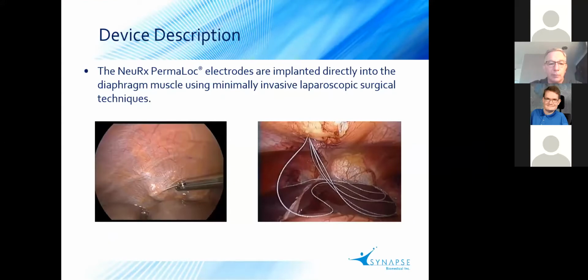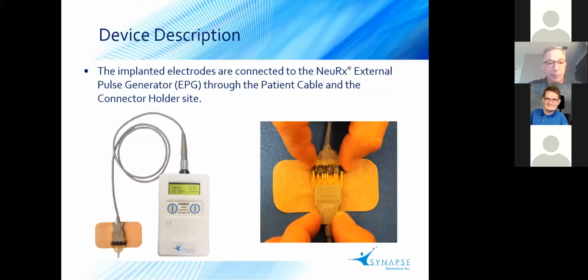First being the electrodes. The PermaLoc electrodes are the electrodes that are implanted directly into the diaphragm muscle using minimally invasive laparoscopic surgical techniques. Picture on the left of this slide shows how the surgeon inserts the electrode into the diaphragm, and then the picture on the right shows the electrodes after all have been implanted and then coming out of the patient's abdomen. It's important to remember that our system is a percutaneous system, so there will be about 2 inches of electrode exiting the skin at a predetermined exit site.